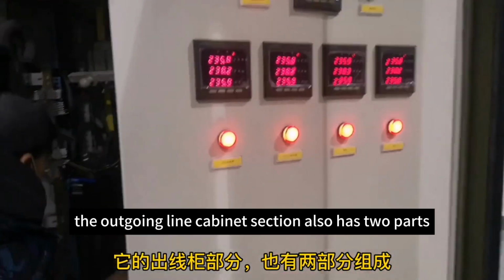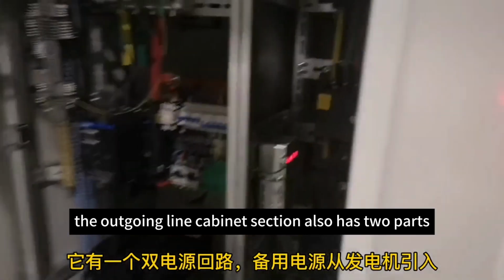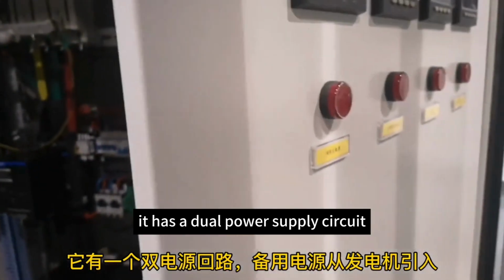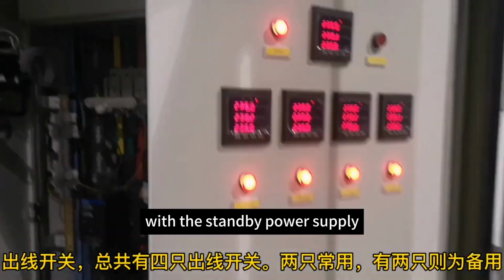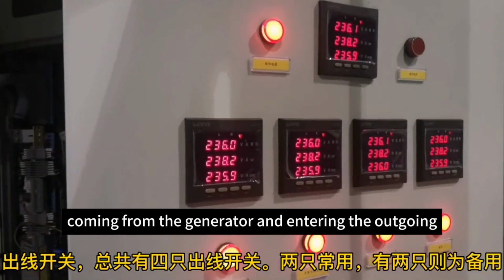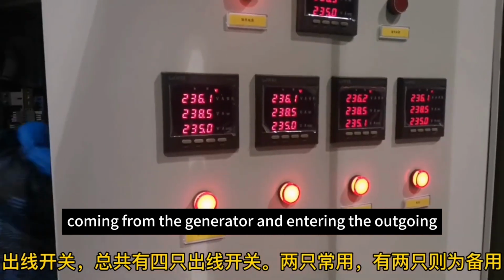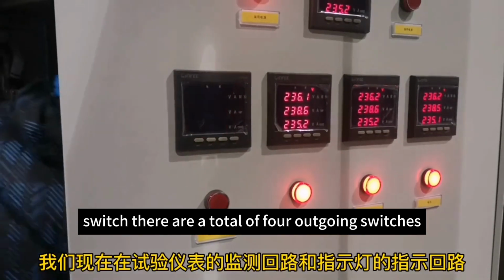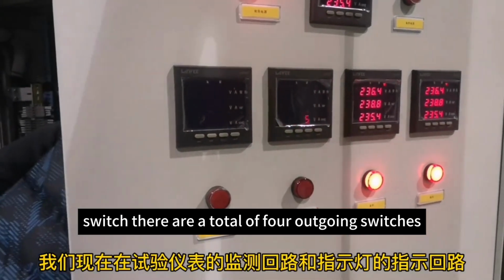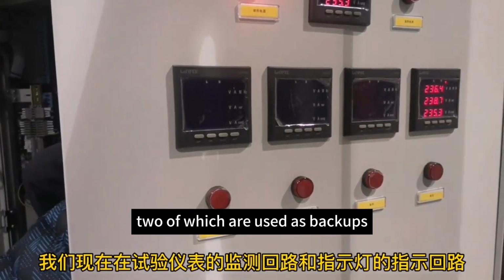The outgoing line cabinet section also has 2 parts. It has a dual power supply circuit with the standby power supply coming from the generator and entering the outgoing switch. There are a total of 4 outgoing switches, 2 of which are used as backups.